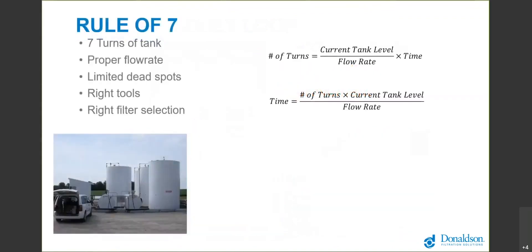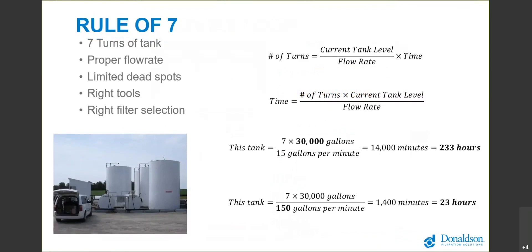Here's a different application where this customer had four 20,000 gallon tanks. If the tanks weren't completely full they had about 30,000 gallons of diesel on site. By the math, that's just not really functional to kidney loop. Even if you increase the flow rate on the pump from 15 gallons a minute to 150 gallons per minute, 23 hours is not achievable.